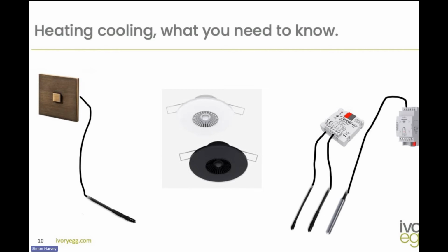Now, you might be saying to yourself, it's a strange place to take a temperature. The truth is, the best place to take a temperature in a room is on the roof — it has less interference from windows, doors, people moving, and so on. The only thing we have to carefully account for is how high the roof is, so we usually offset the room temperature by about 1 degree for every meter in height off the floor level.